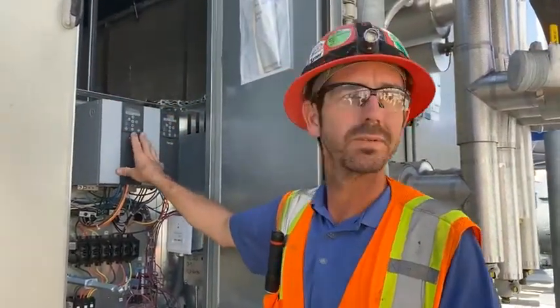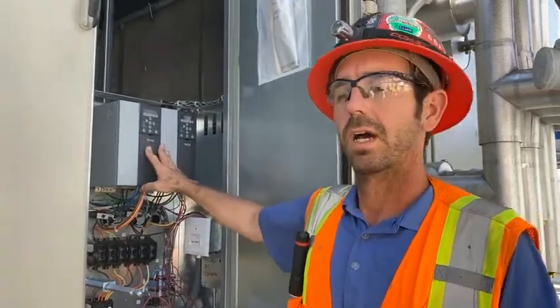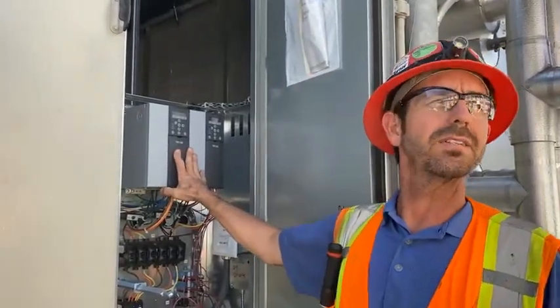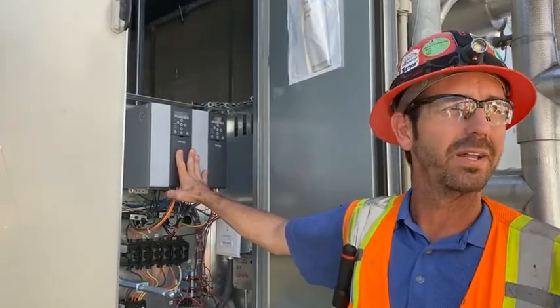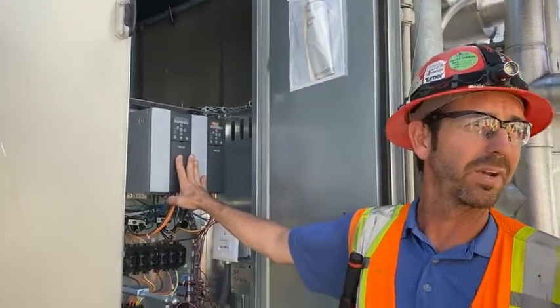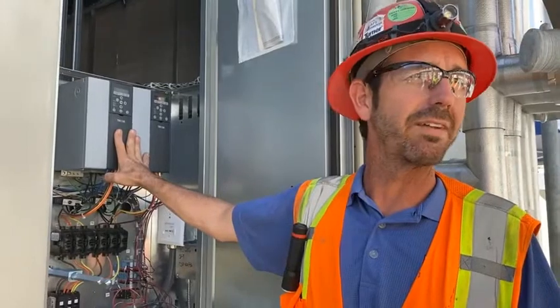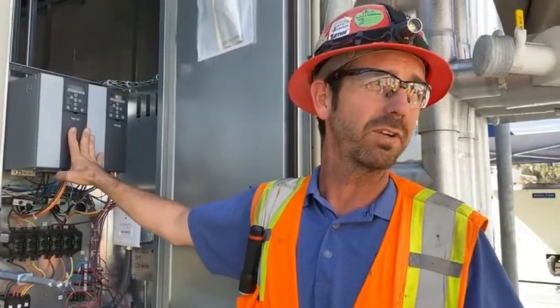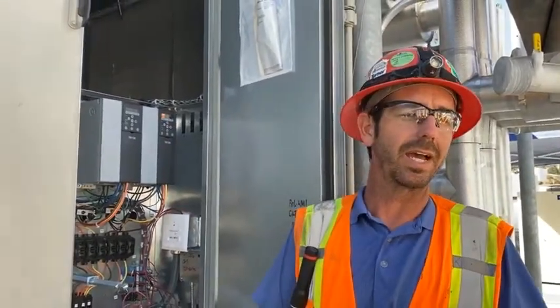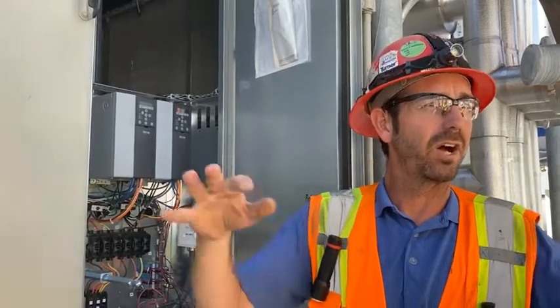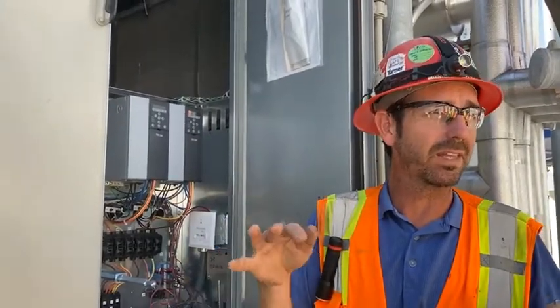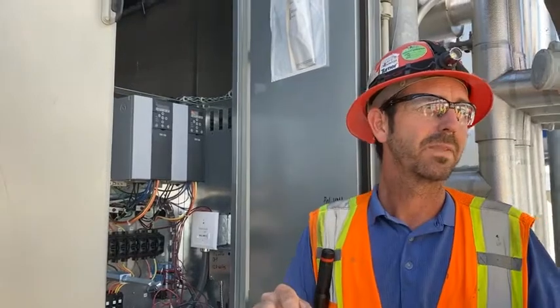So what is the static that's maintaining the duct? That was set up during the balance process. Off the top of my head, I don't know it, but it's going to be in the front. It's going to be in the computer. And if for some reason we ever lose that information, it'll be on the balance report that gets turned over to you guys.